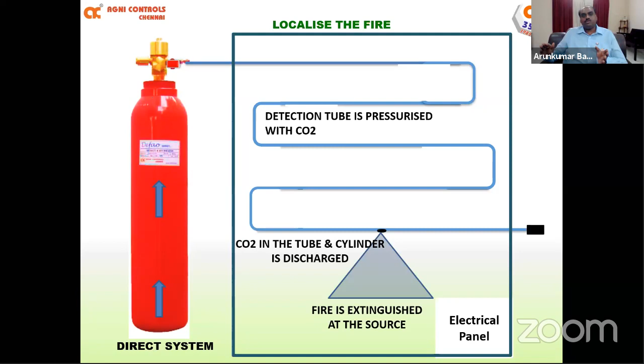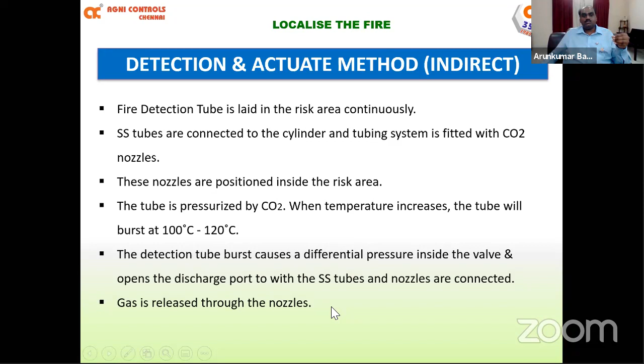Here we use SS tubings or small pipings, and we connect a real nozzle into the cabinets or risk area. I'll show an animation which will make this easier to understand. In this application, it's the same kind of electrical panel, and we have laid the fire detection tube inside this electrical panel as the risk area.